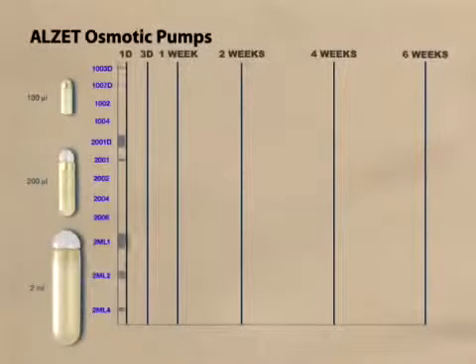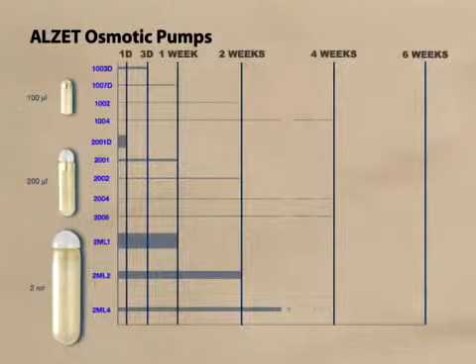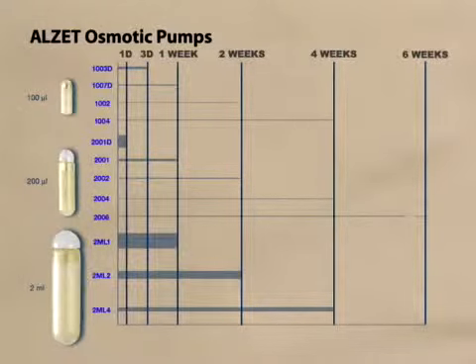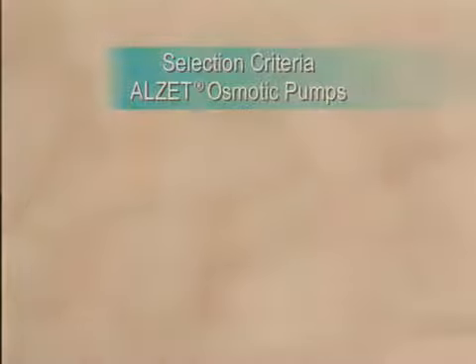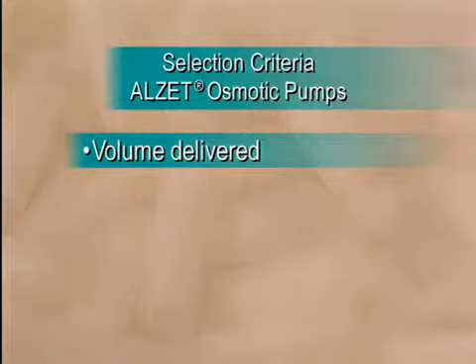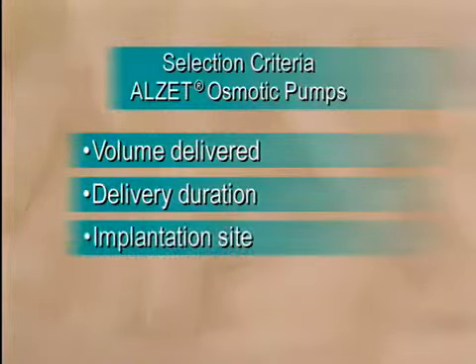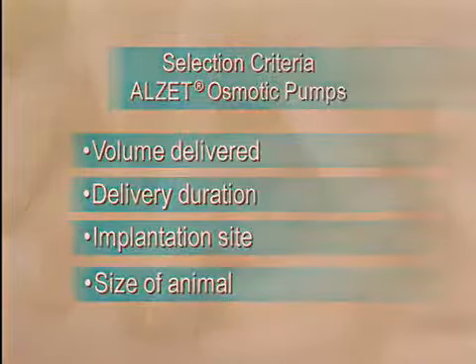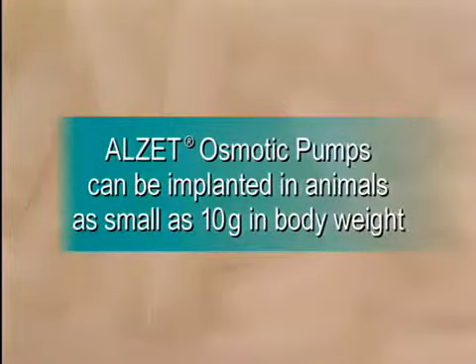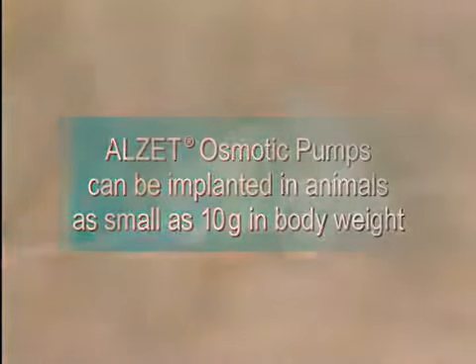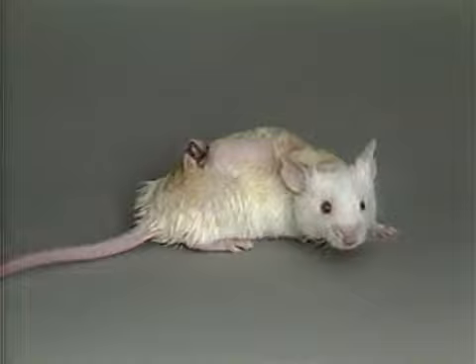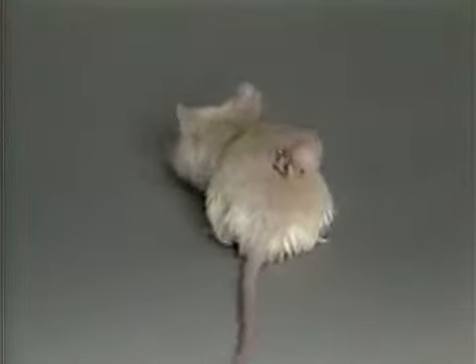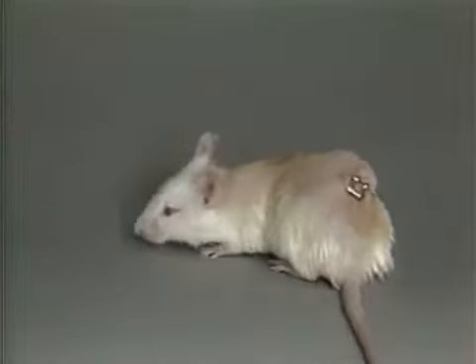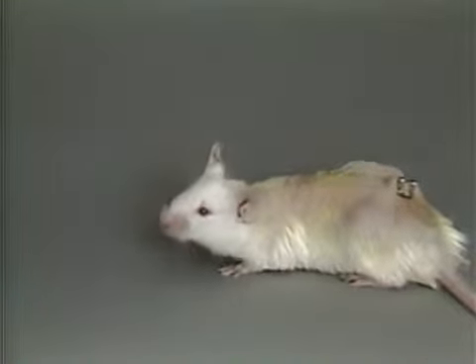ALZET osmotic pumps have programmed delivery rates from 0.11 microliters per hour to 10 microliters per hour. Their operational duration ranges from 1 day to 6 weeks, depending on the model and the delivery rate that is selected. When choosing a pump, consider the volume to be delivered, the delivery duration needed, the implantation site, and the animal's size. The pumps can be implanted subcutaneously in animals as small as 10 grams in body weight. This adult mouse underwent subcutaneous implantation of a 200 microliter pump just moments earlier. When properly implanted, the ALZET osmotic pump causes no evident discomfort to the test animal.